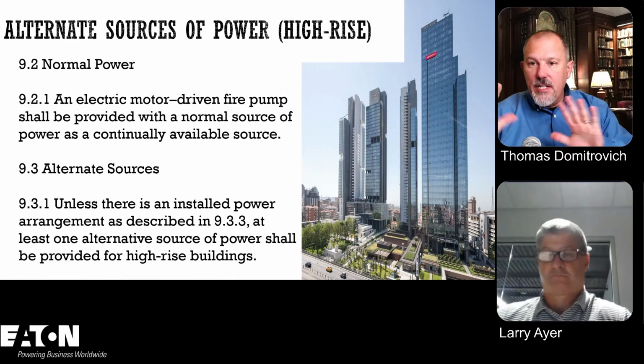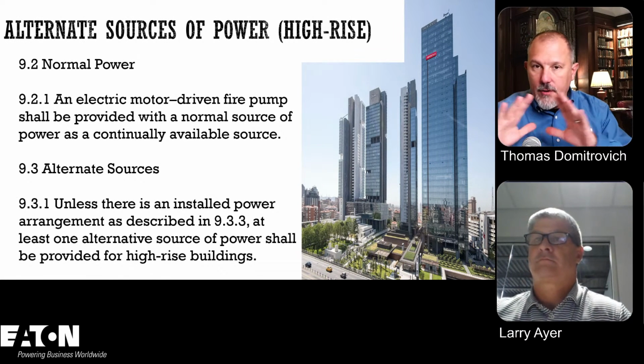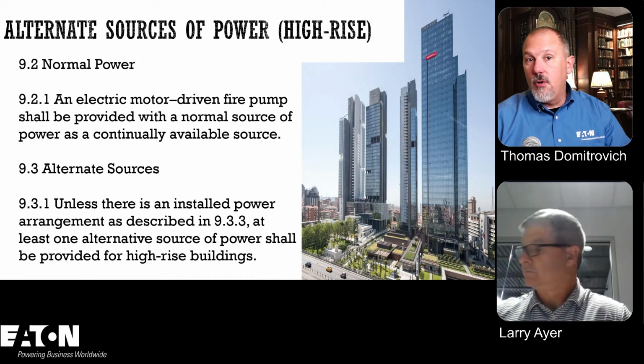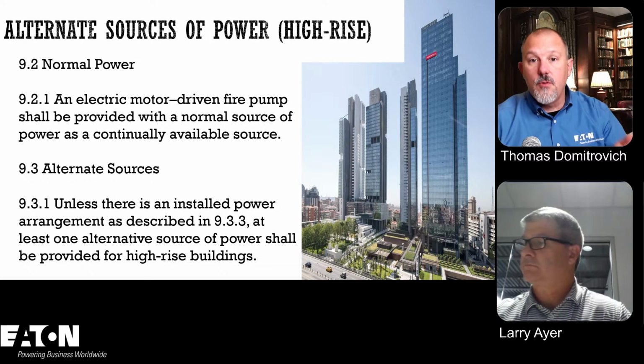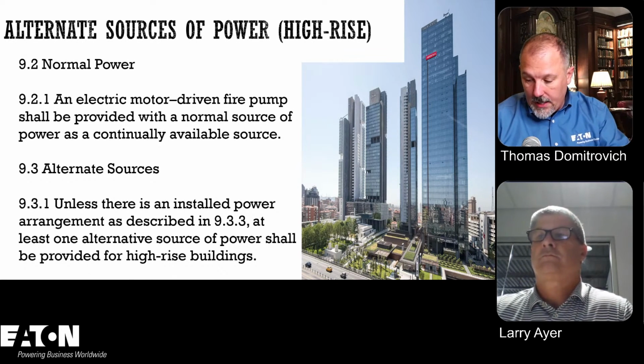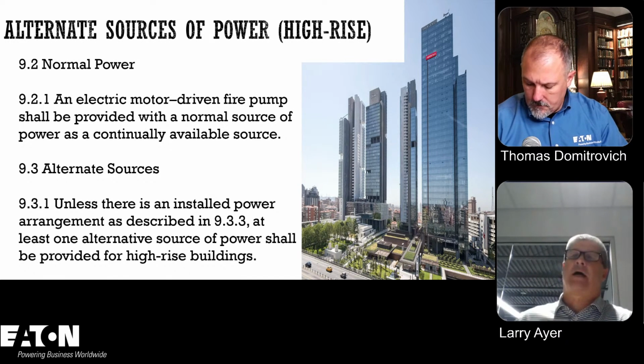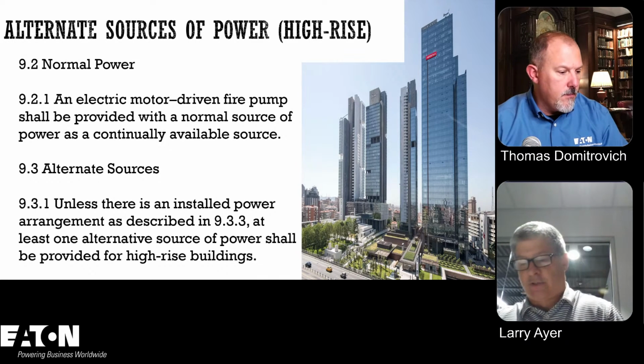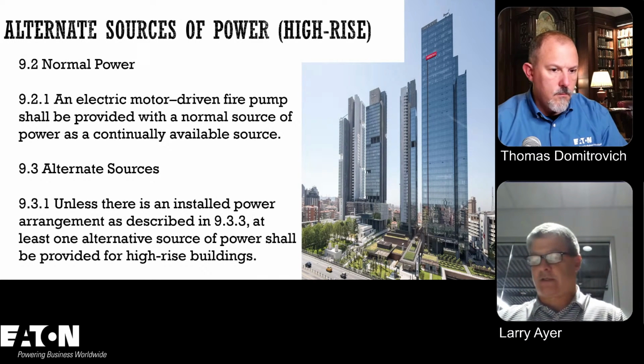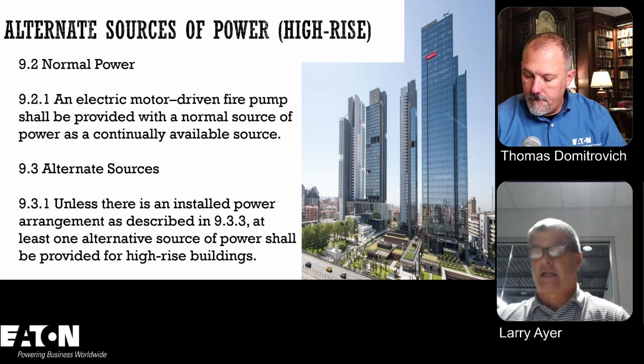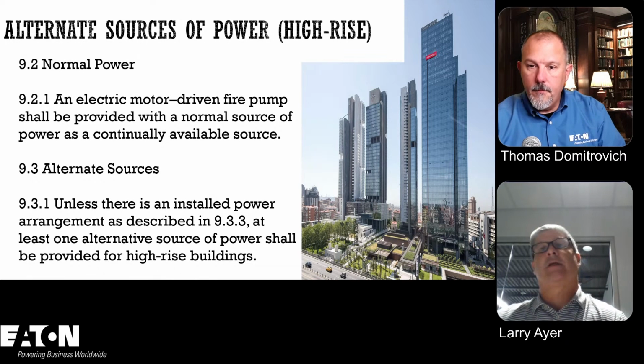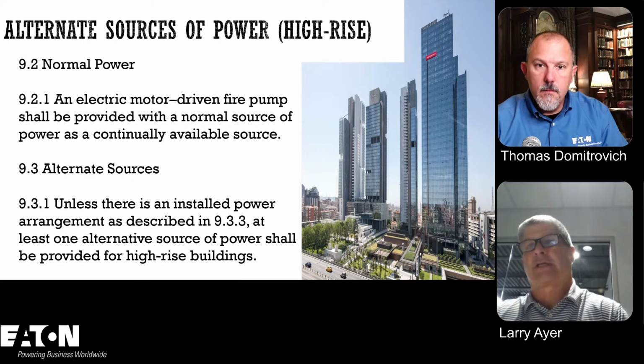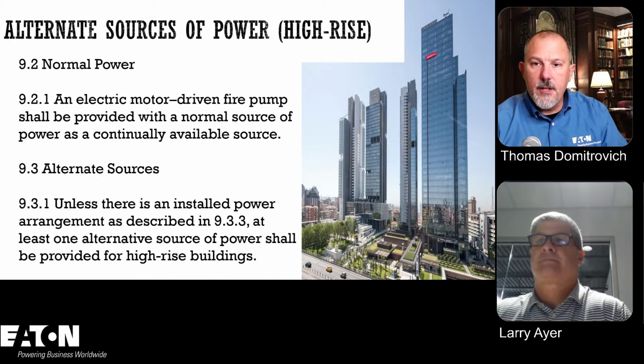Now, all of that we just talked about sounds a little complicated, but again, you have these options. The wrench that we're going to throw into the whole discussion is when you're dealing with a high-rise building, because there are special requirements that you have to follow as part of NFPA 20. I think NFPA 20 was the location. There wasn't anything in 695, right? Correct. There's nothing in there that talks about alternate sources of power for high-rise. There are things in Article 700: if it's an emergency system and it's a high-rise, you need to provide an alternate source of power. But for fire pumps, where it mentions high-rise is specifically in NFPA 20. Right. So this is telling us that you need an electric motor-driven fire pump with a normal source of power as a continually available source.